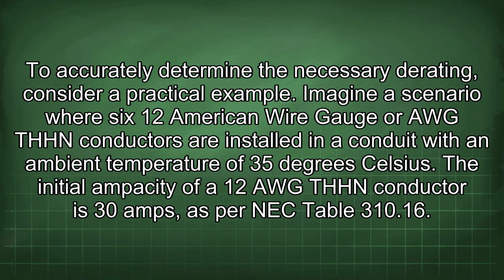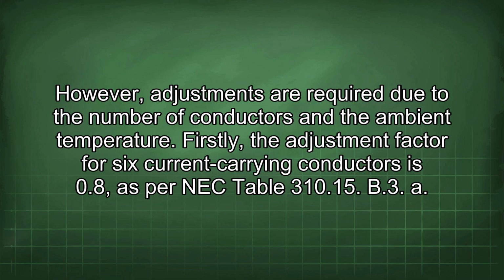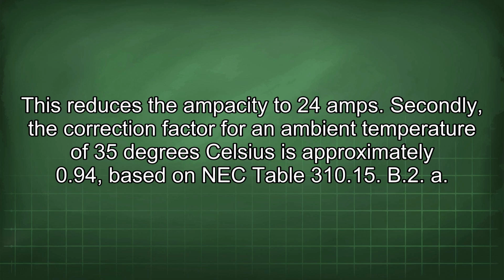To accurately determine the necessary derating, consider a practical example. Imagine a scenario where 6 12 American wire gauge or AWG THHN conductors are installed in a conduit with an ambient temperature of 35 degrees Celsius. The initial ampacity of a 12 AWG THHN conductor is 30 amps, as per NEC Table 310.16. However, adjustments are required due to the number of conductors and the ambient temperature. Firstly, the adjustment factor for 6 current carrying conductors is 0.8, as per NEC Table 310.15(B)(3). This reduces the ampacity to 24 amps.